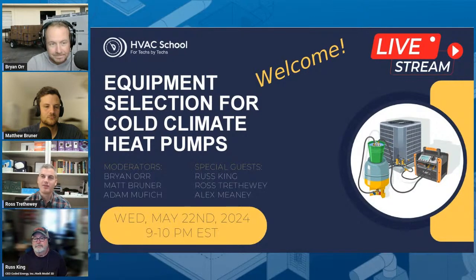Yeah. We got all four to deal with. We got to humidify buildings in the wintertime. We got the dry air, right? We have to obviously provide cold climate heat pumps to heat the buildings. But we also need to cool. We also need to deal with latent loads and dehumidification. So we've got the full Monty in terms of hitting all four. So a lot of our high performance builds, we're going to have a cold climate heat pump to do heating and cooling. We're also going to have a ducted dehumidifier to handle the latent loads. And a lot of times we're going to have a steam humidifier to add moisture to these buildings.